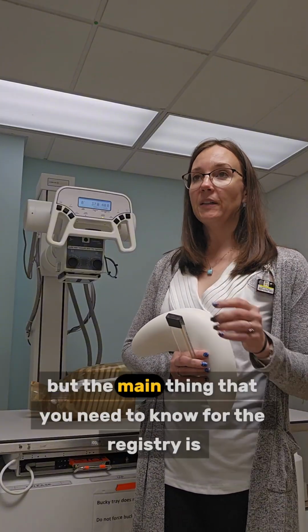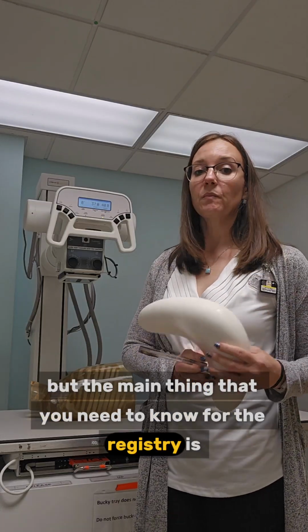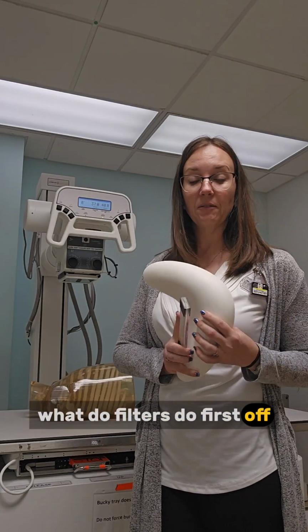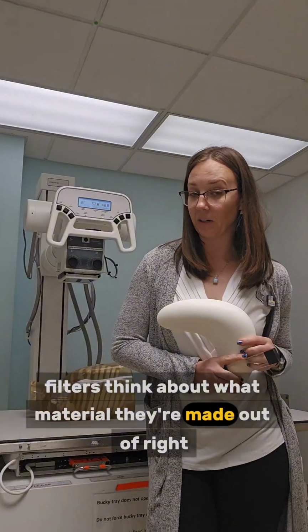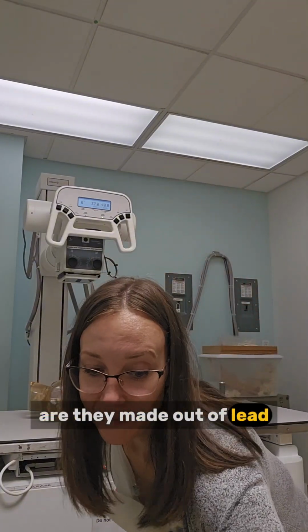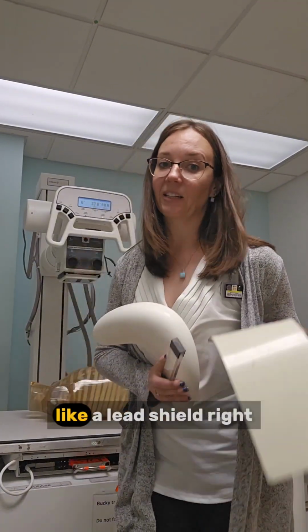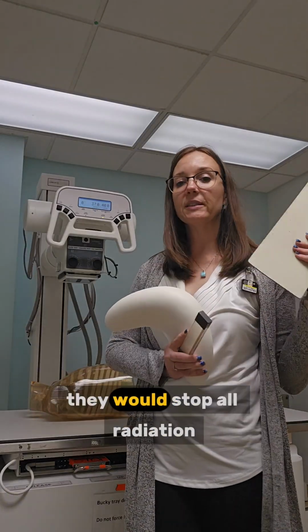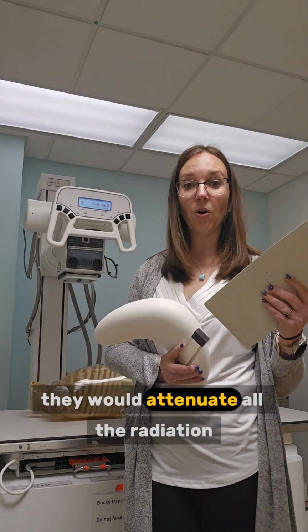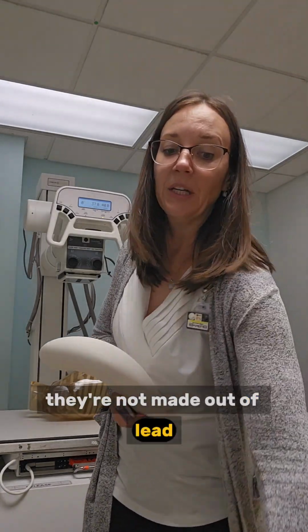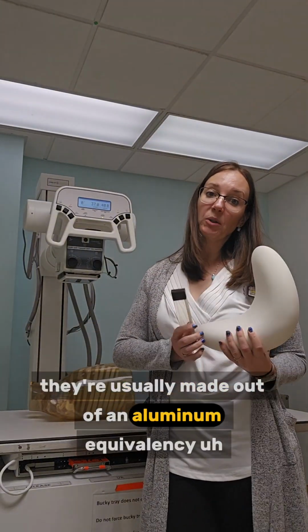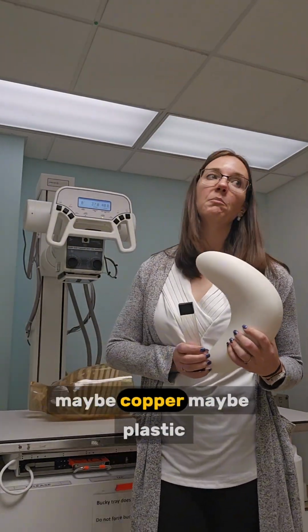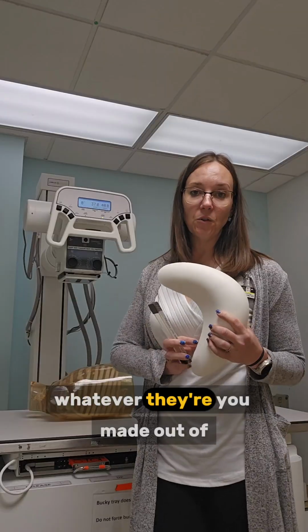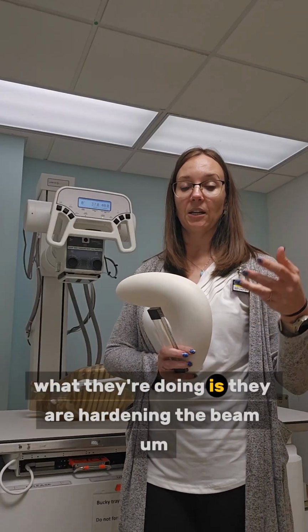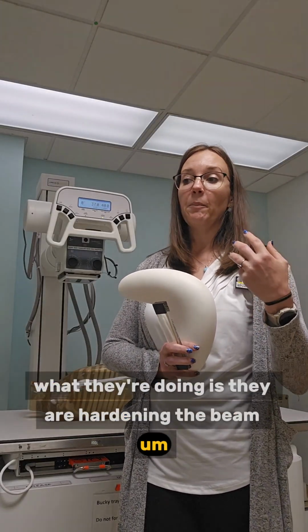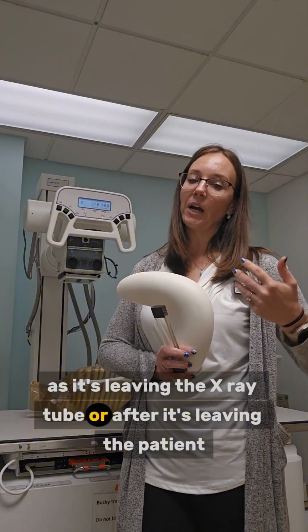But the main thing that you need to know for the registry is what do filters do? First off, think about what material they're made out of, right? Are they made out of lead? If they were made out of lead, like a lead shield, they would stop all radiation. They would attenuate all the radiation. They're not made out of lead. They're usually made out of an aluminum equivalency, maybe copper, maybe plastic, whatever.